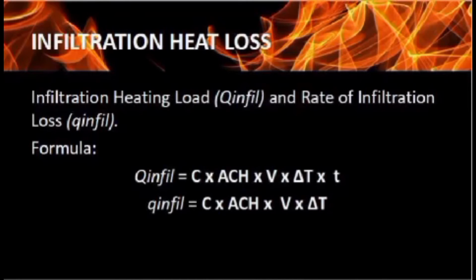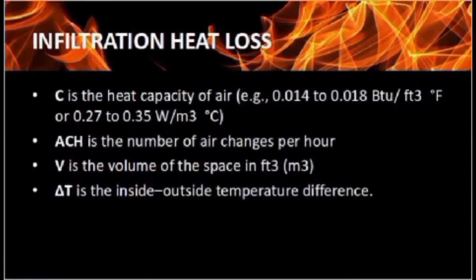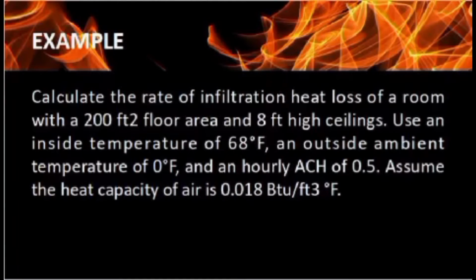So here is the formula of infiltration heating load and rate of infiltration loss. Infiltration heating load is equal to C times ACH times V times delta T times T. And rate of infiltration loss is equal to C times ACH times V times delta T. C is the heat capacity of air, ACH is the number of air change per hour, V is the volume of the space in cubic foot and cubic meter. Delta T is the inside-outside temperature difference.